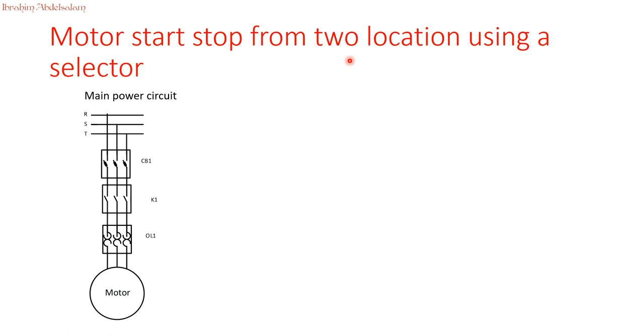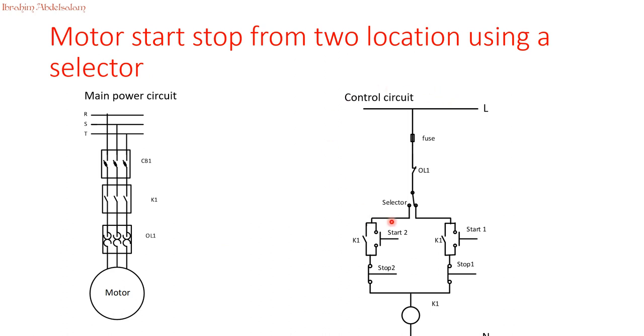Start/stop from two locations using a selector: the power circuit remains the same and is not affected by the control changes. In the control circuit, we have a selector, start one, start two, contactor one latch, contactor one and two stop buttons. The overload is moved so that whether the selector deflects right or left, the power will be interrupted in case of overload.